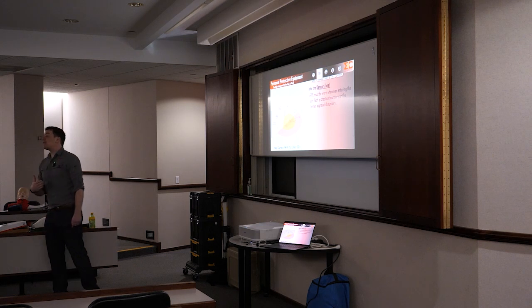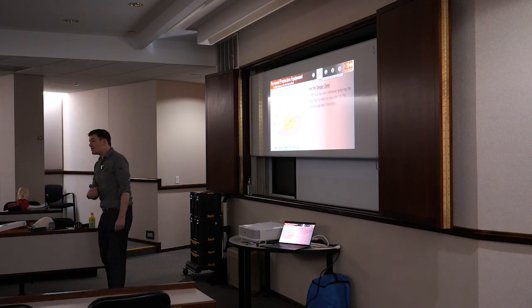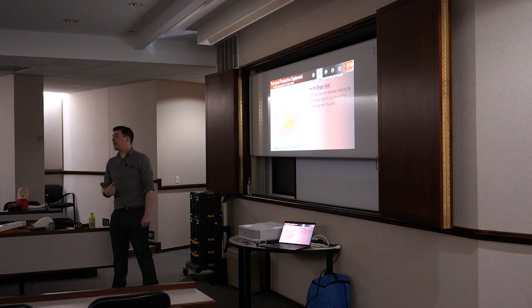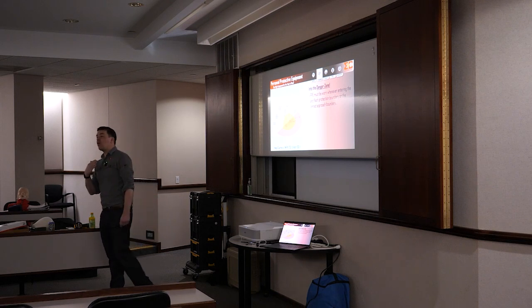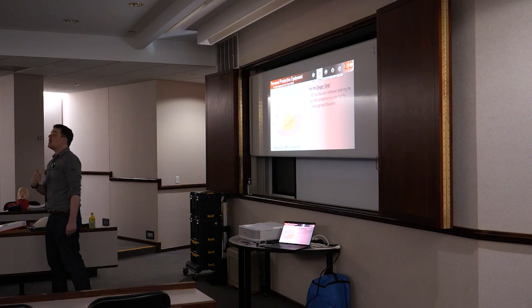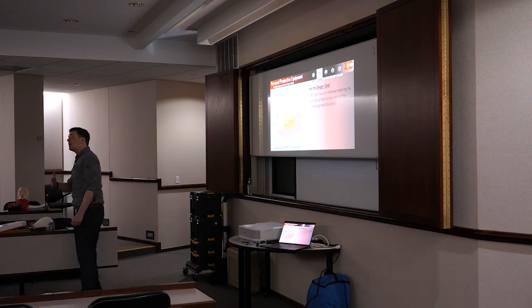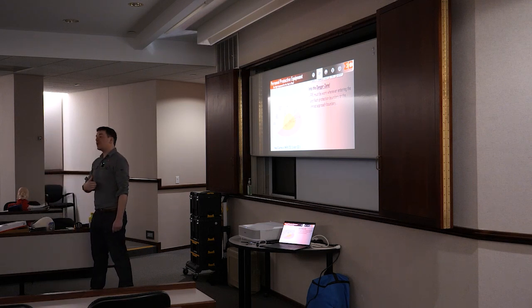So systems can be layered to achieve that, and it's important to understand for things like our arc flash suits, they are wonderfully light. They get that rating by being worn all at once. You may not achieve the same level of rating if you're wearing just the jacket. I'm not certain, but the reason you have both the bib and the jacket overlapping is because this is usually where you have the greatest level of incident energy exposure and the greatest amount of surface area absorbing that potential incident energy.